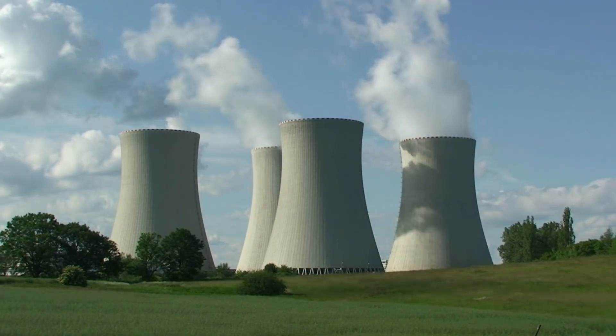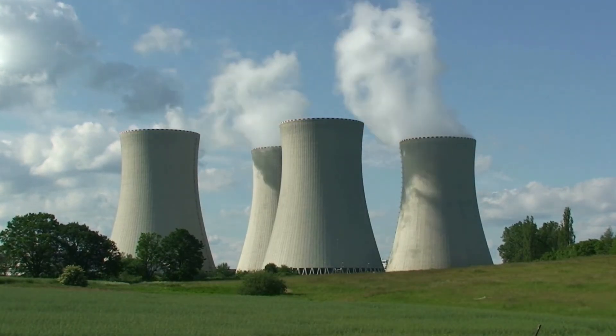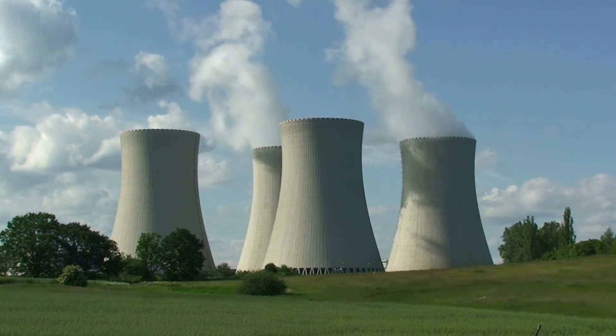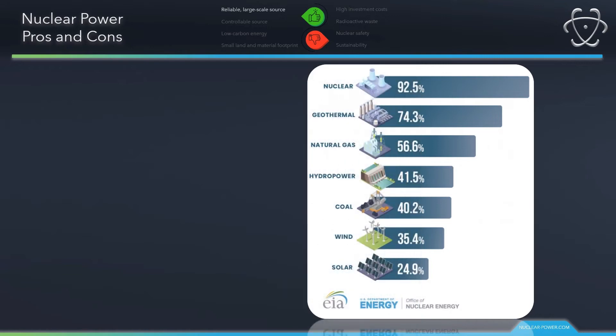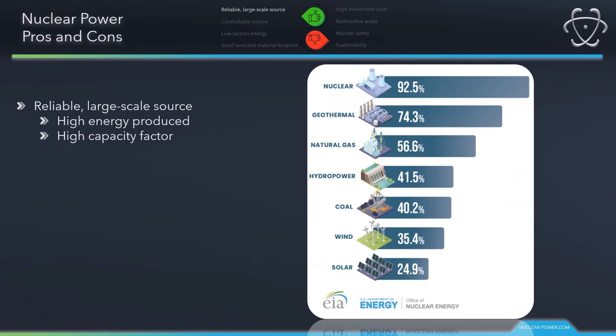Now we will discuss the most mentioned advantages. Nuclear power is a reliable, large-scale, controllable, low-carbon energy source with a small land footprint. The term reliable means that nuclear energy has by far the highest capacity factor of any other energy source. According to the US DOE, nuclear power plants are producing maximum power more than 92% of the time during the year — nearly two times more than natural gas and coal units, and almost three times more reliable than wind and solar plants. Nuclear power plants are considered baseload sources of electricity, designed to operate at close to maximum output continuously, apart from maintenance refueling outages typically every one and a half to two years.